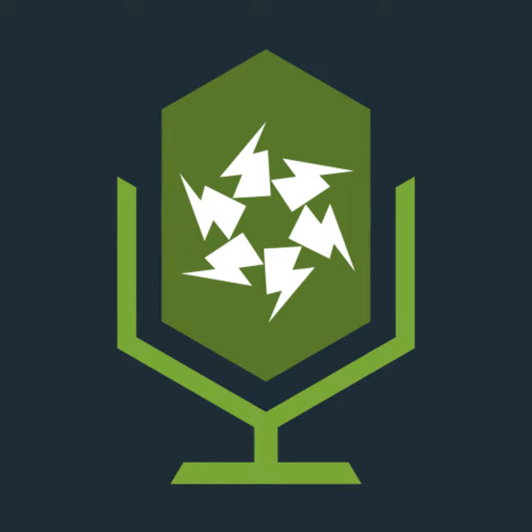The means of operating handle or push button devices for emergency switching off shall be clearly identified, preferably by colour. If a colour is used, it will be red with a contrasting background, such as yellow. Now, it's important to understand that that's not an accident. They do have a red on yellow contrasting background so that it makes it pop. This photo is not in a very good light for the switch, but you can kind of make an understanding of that there. The reason why quite often you'll see that red on a yellow instead of red on anything else is that in lower light the yellow helps the red pop and stand out.